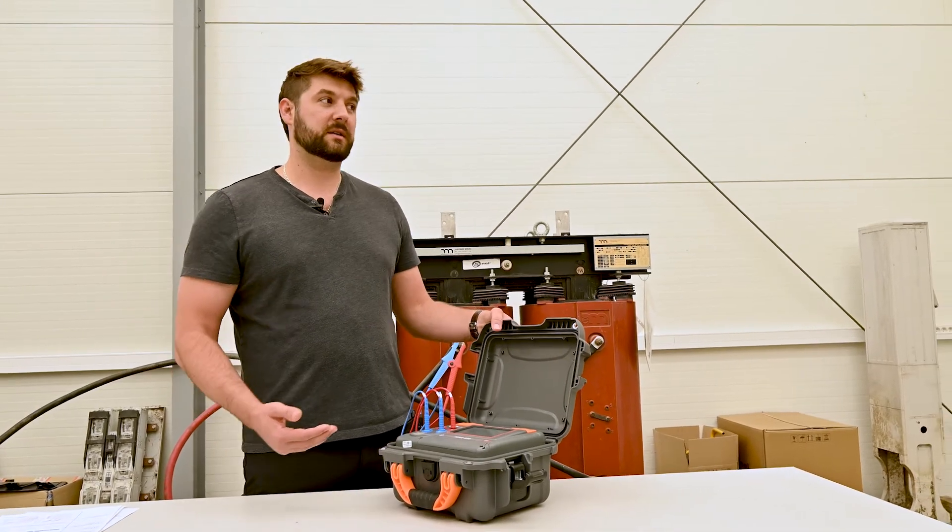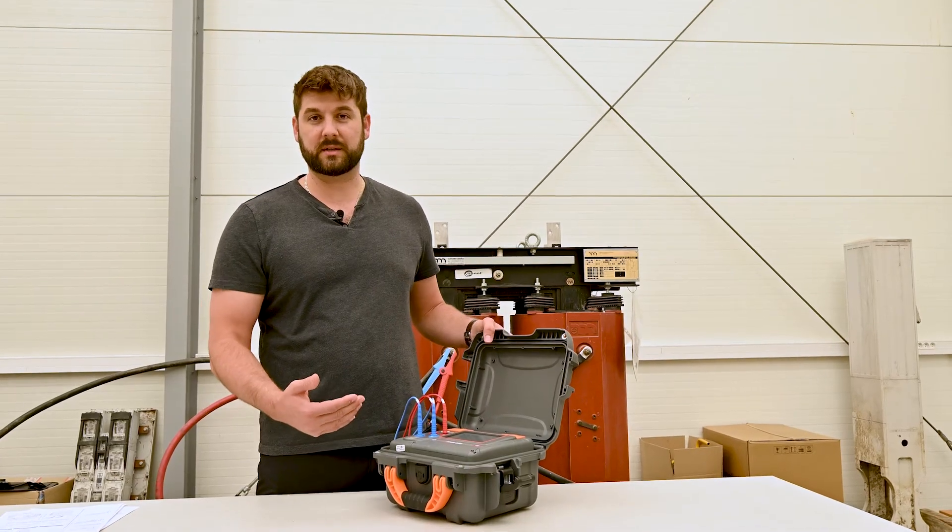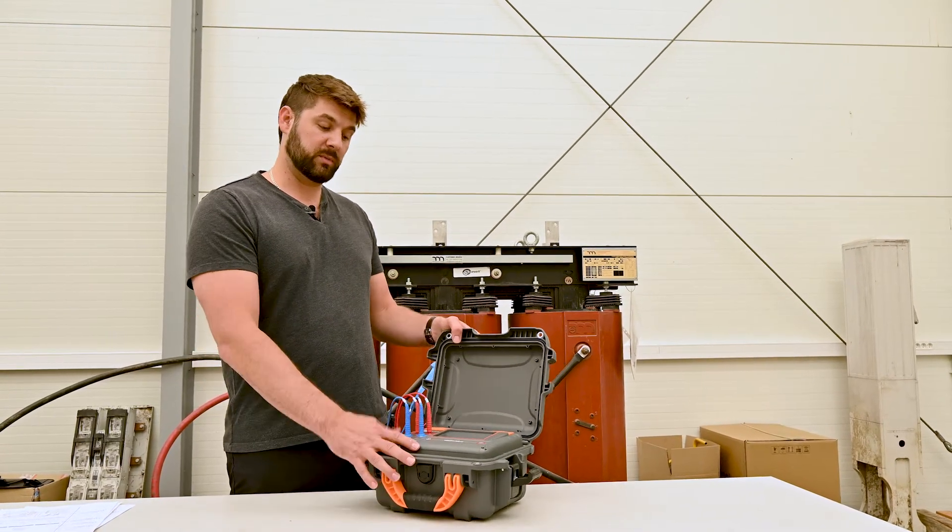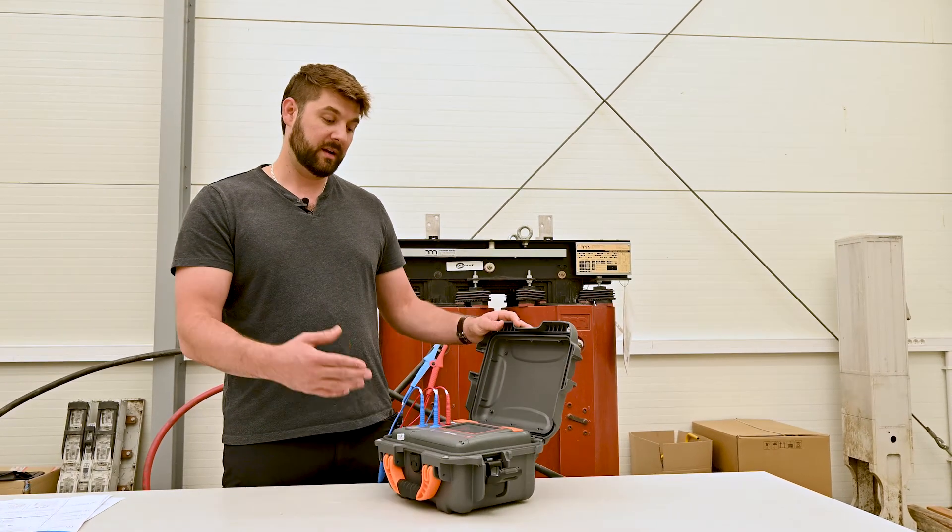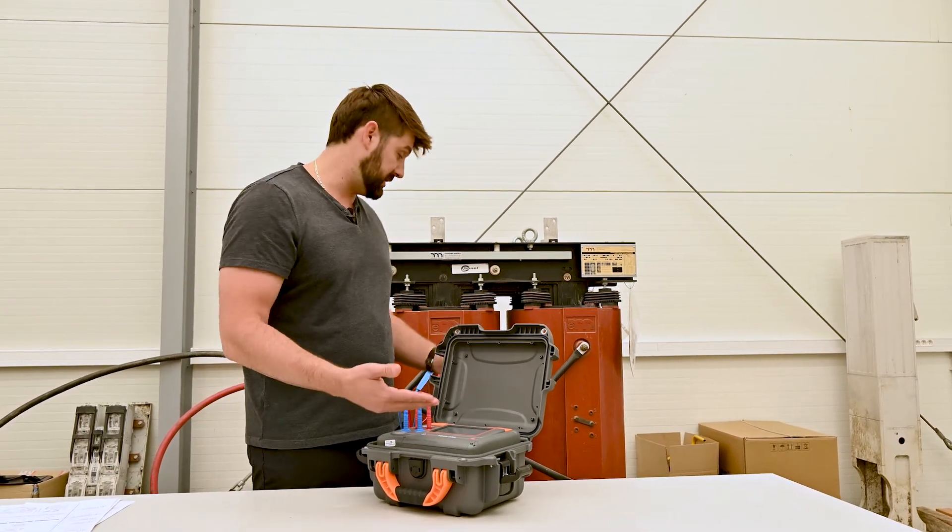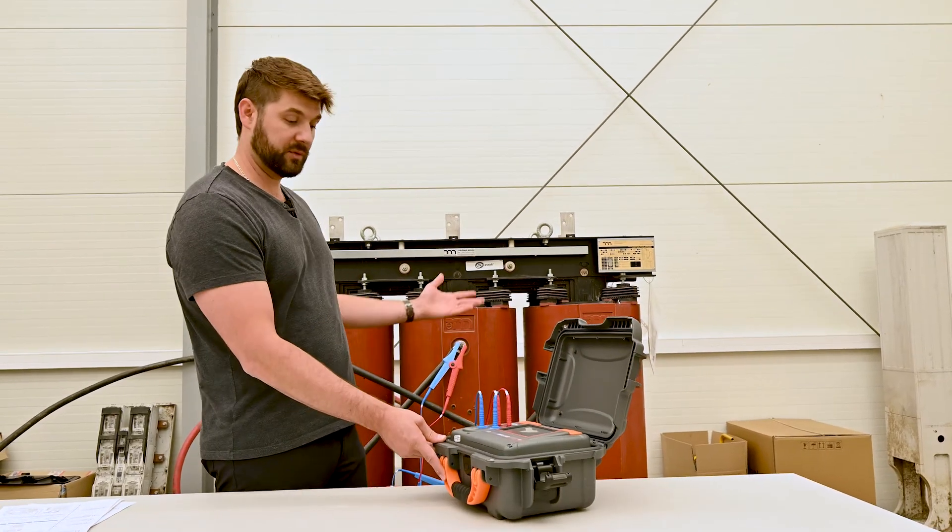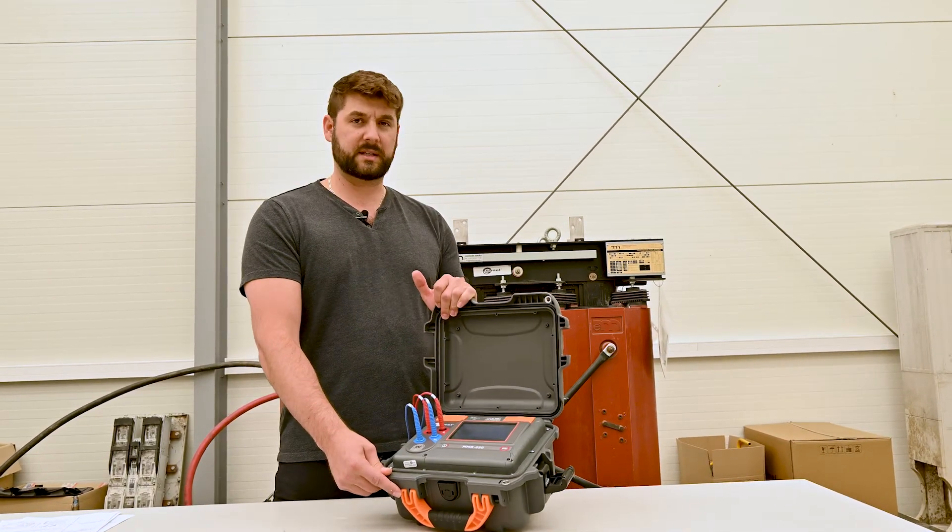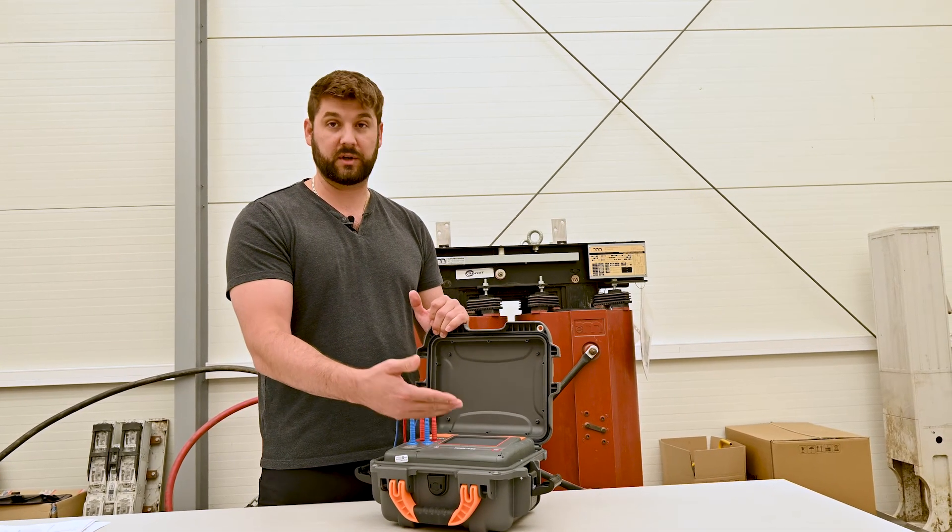If you're testing inductive objects, it does take more time because you have to overcome the inductance to get a stable current. But this instrument will also allow you to demagnetize the core of the winding after you finish. As you can see, I just demagnetized this transformer across the B phase after we were done testing it. It takes a few minutes, but now it says core demagnetization process finished.